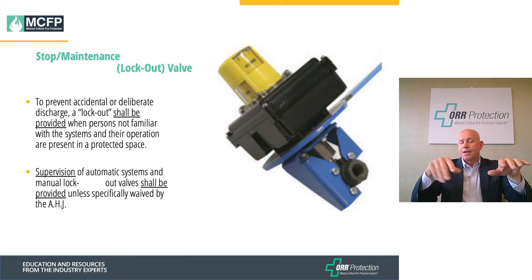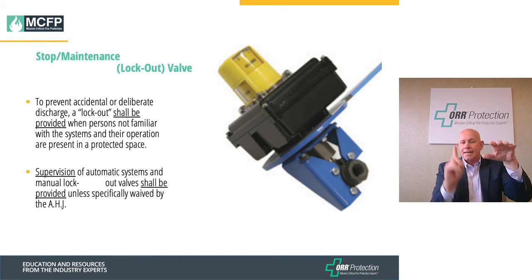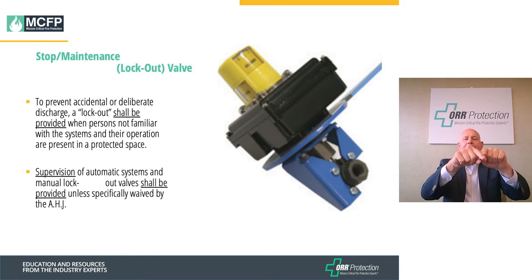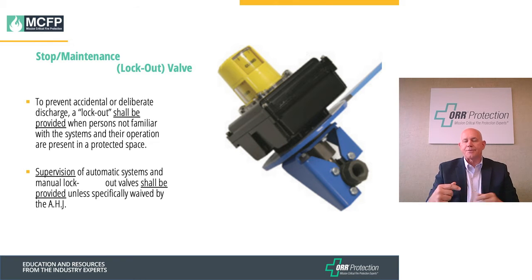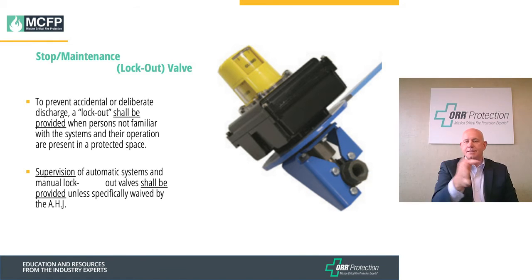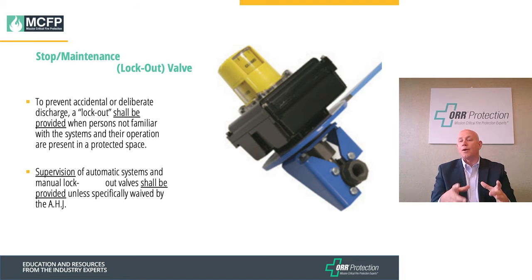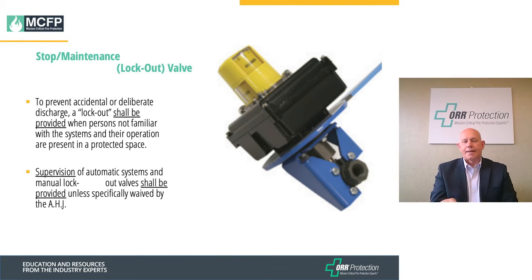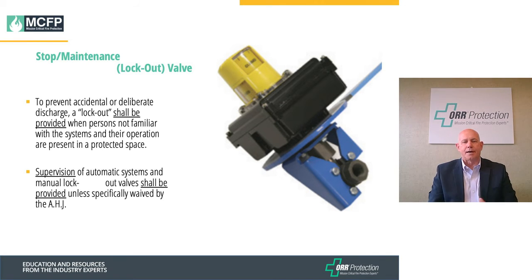The valve must have both mechanisms: the lockout valve capable of accepting a physical lock in the off position, and electronic supervision providing notification back to the panel — a two-stage valve configuration. For multiple zones off a low pressure tank, the code does give some tolerance: as long as you're not working on any other zones live, you can use the master valve at the tank as the main lockout valve. Putting a lockout valve on every individual line is an option, but not required by code.